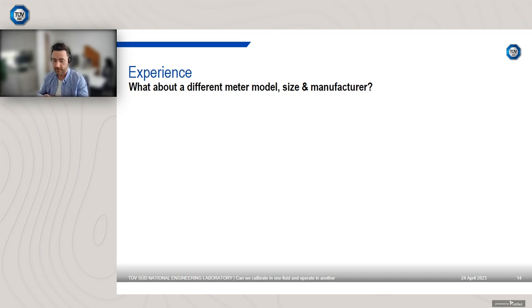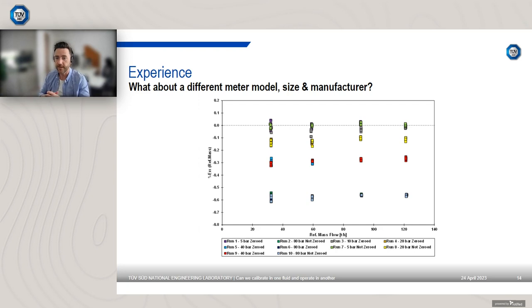Now this is the webinar today talking about calibrating Coriolis meters, but I can't show you too much. Simply I don't want to go through too many different meter types, but I do have an additional one here to show you today. So again, a different meter, but you can see here that we also have a significant underread once again. Now in the legend it looks quite messy. This was another experimental program I looked at to see whether zeroing or not zeroing the device appeared to affect the results. And by and large, for the higher flow rates, as expected, it didn't.